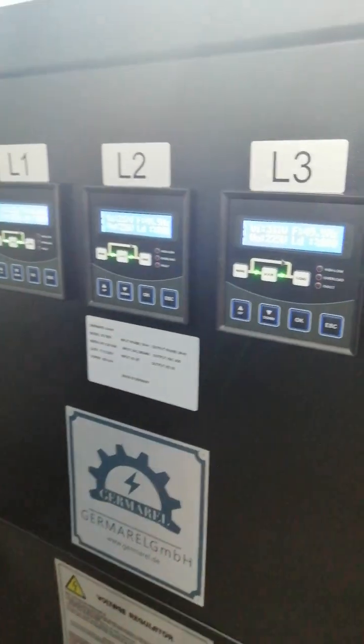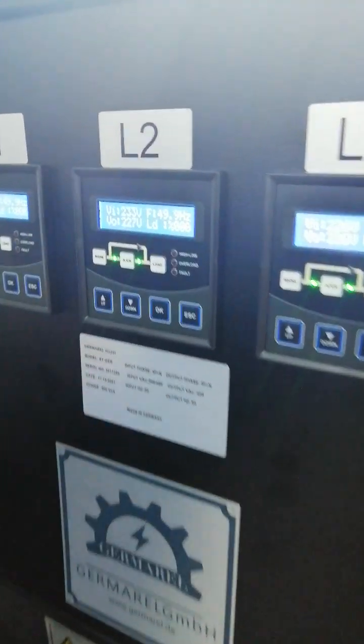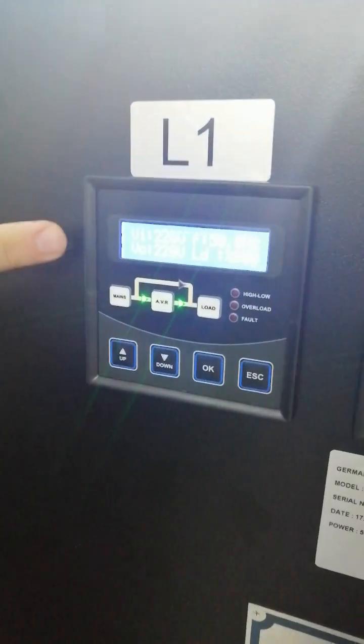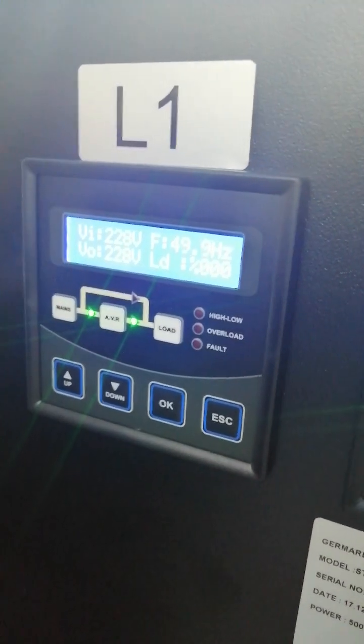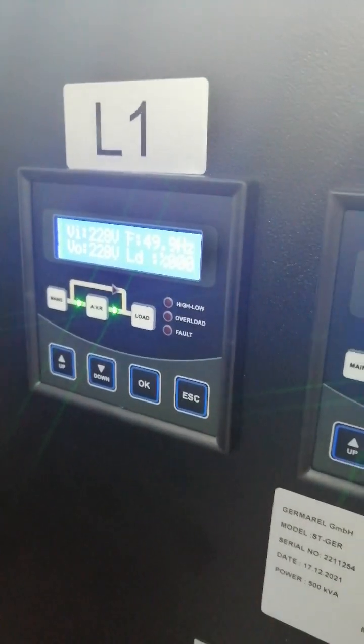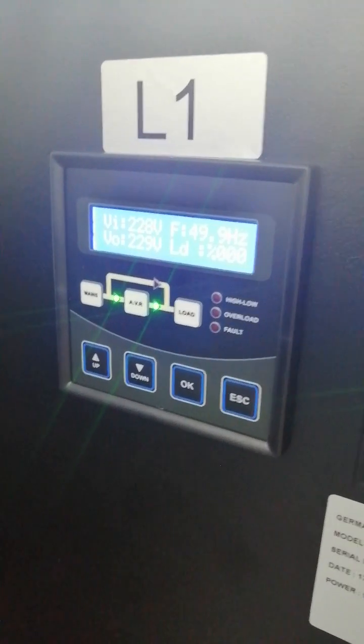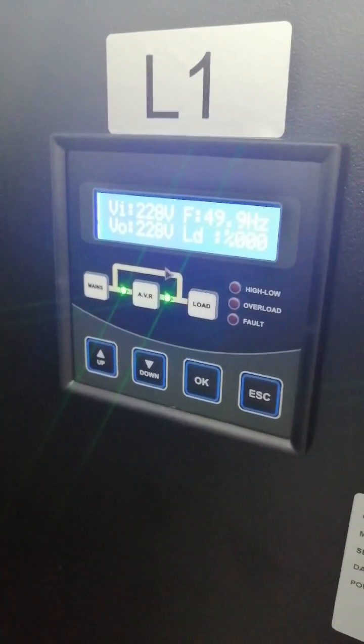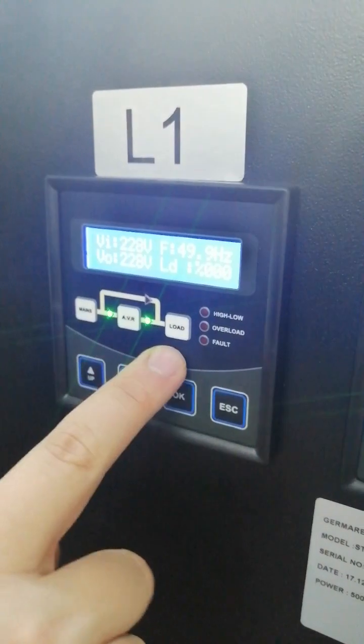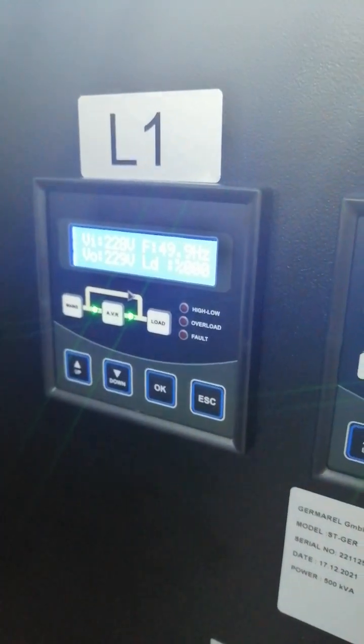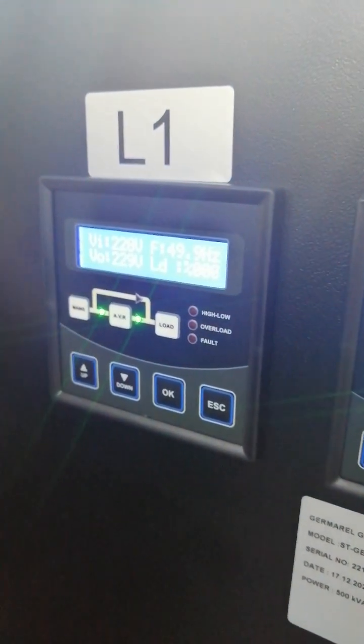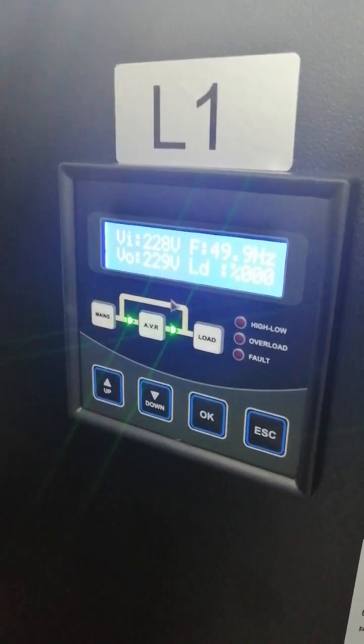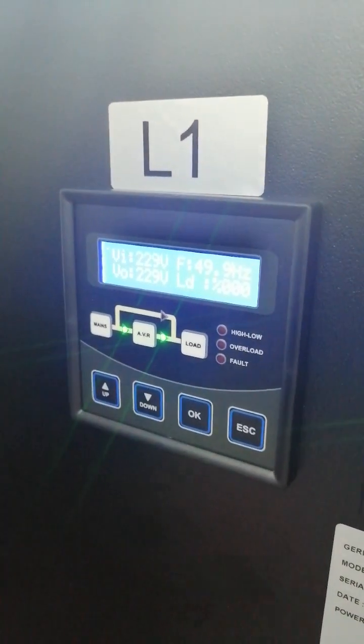We have three displays. You can follow up each parameters on the displays: input voltage, output voltage, frequency, load percentage. Right now zero percent because it's not under load. We are making test. You can follow up the general status on the mimic diagram, on the block diagram. Mains means grid voltage. AVR means regulator and load is load.